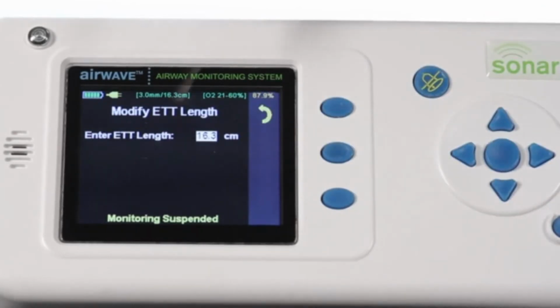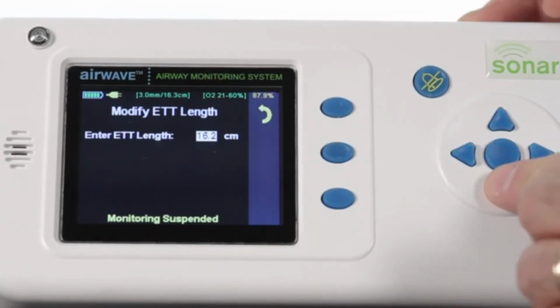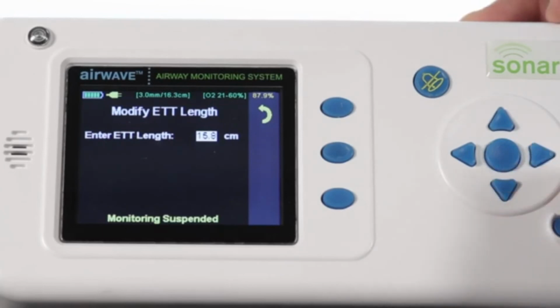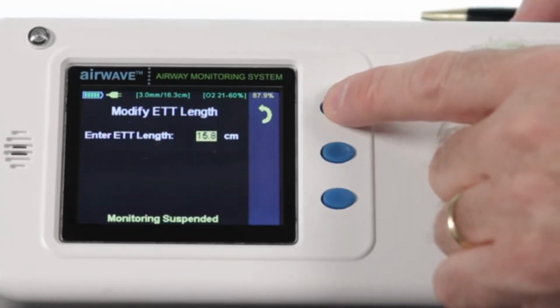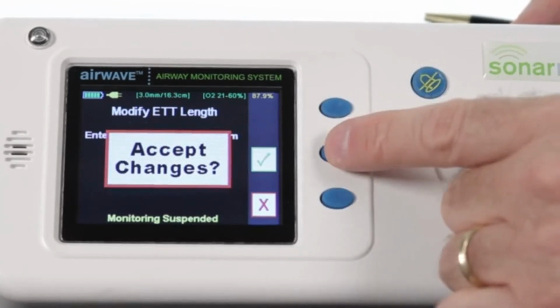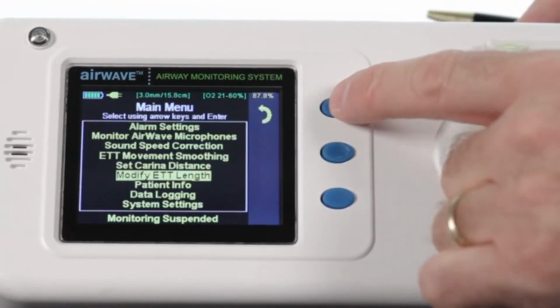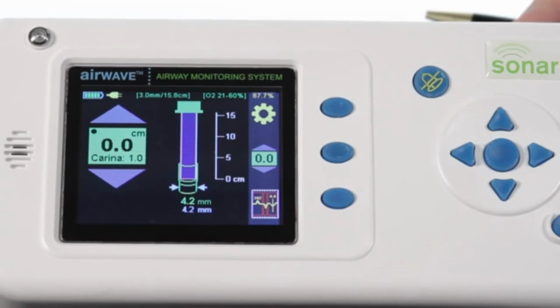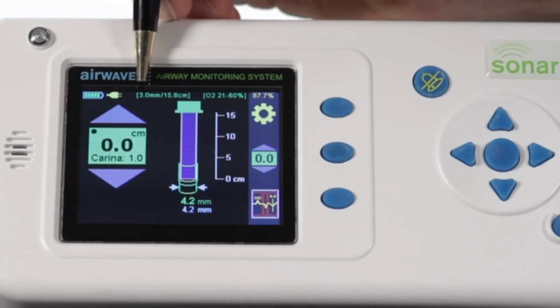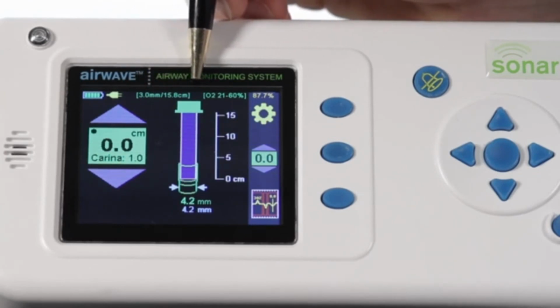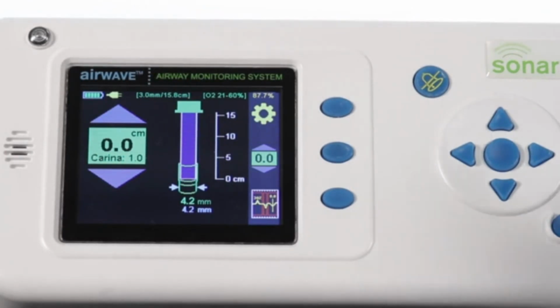We'll now reduce this length to 15.8 centimeters. We hit the center to enter button again. We hit the return button. We tell the monitor to accept those changes and return back to the monitoring screen. At this point, the monitor has been adjusted for the ET tube length, and you can see that as the new length is displayed at the upper part of the monitor in the center, showing you that the tube has been reduced in length.